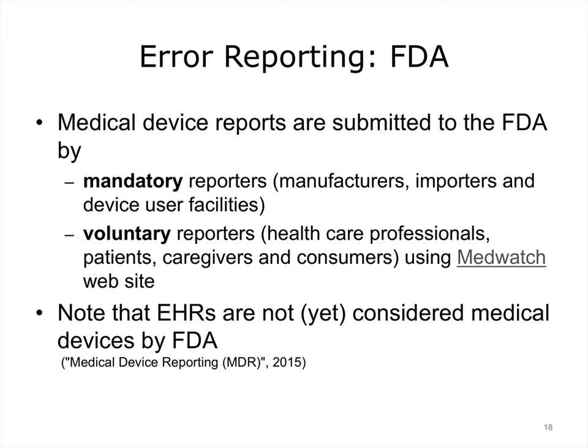Mandatory reporters — manufacturers, device user facilities, and importers — are required to submit certain types of reports for adverse events and product problems to the FDA about medical devices. The FDA also encourages healthcare professionals, patients, caregivers, and consumers to submit voluntary reports about serious adverse events that may be associated with a medical device, as well as use errors, product quality issues, and therapeutic failures.